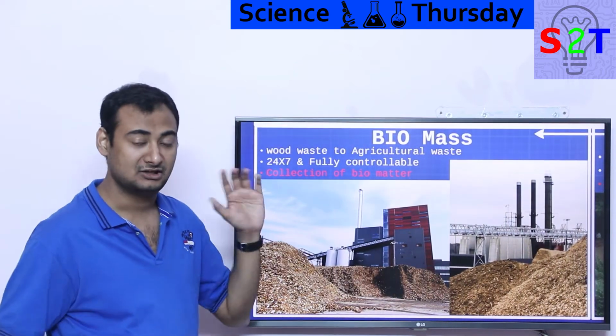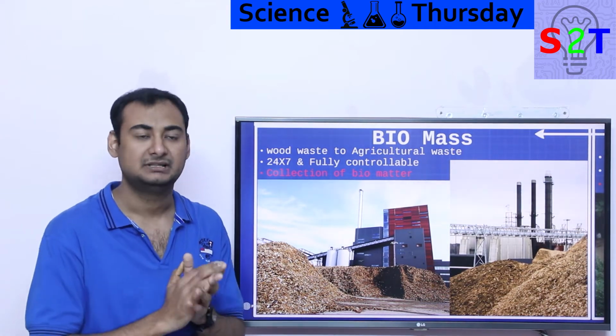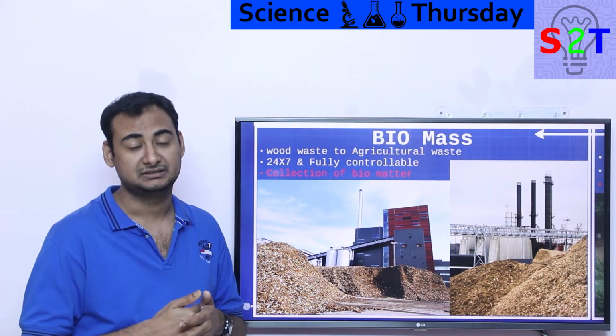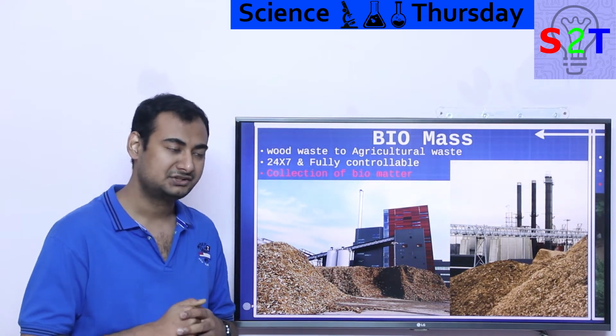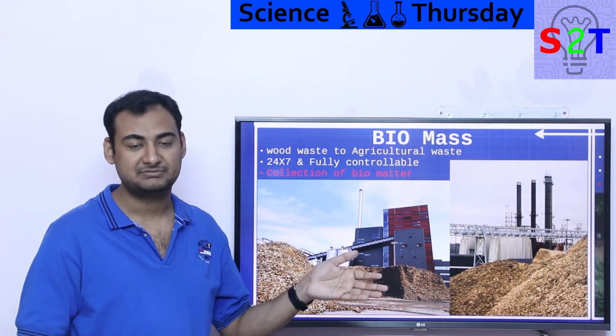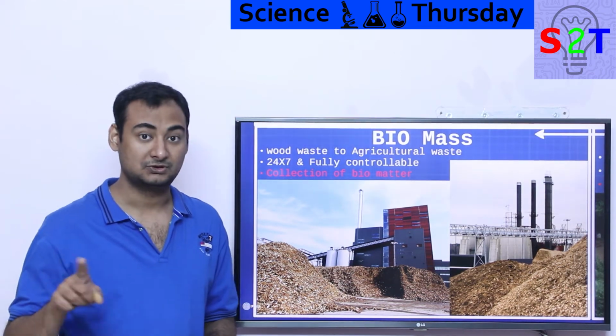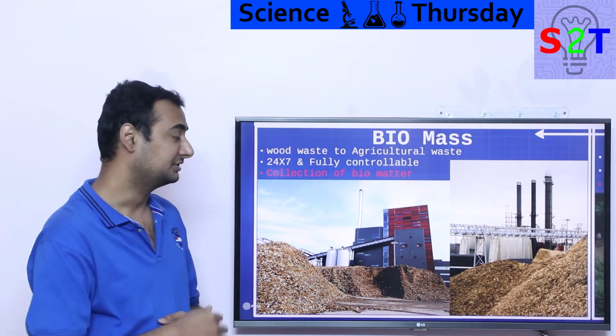Then we come to biomass. Now gas systems generally take the biomaterial and convert it into methane and other stuff. Methane is then burnt for whatever you want to do. Generally people use generators. Sometimes if they have a lot of money, they will use turbines, and if they have a really large amount of money or good connections, they will use a fuel cell. The benefit of a fuel cell is that it is much more efficient. Compared to the 20% you get out of a generator, you get around 40% from a fuel cell, and you get centralized heat output, so you can utilize it properly. So that's one option there.